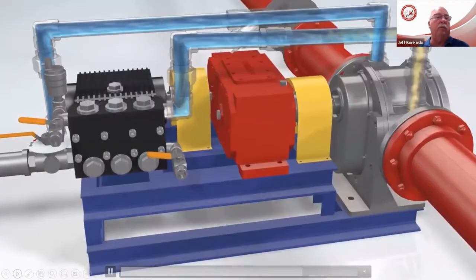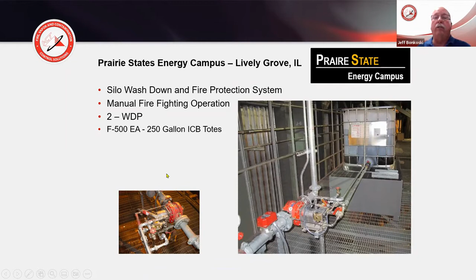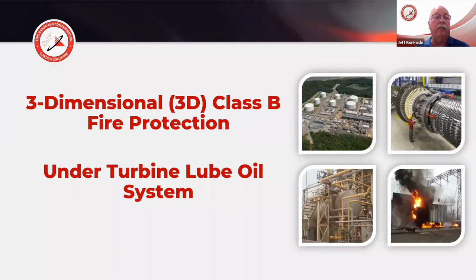Here's an example. We have a tote with a containment, and as you can see, it's elevated, so it's gravity fed. Again, there's no electricity and no pump needed. You have your water driven proportioner and your flow controls. Once the water starts flowing, the pump will activate and draw concentrate up into the water system and the sprinklers, helping to cool. It adds the agent in and works to reduce the soot, toxins, heat and smoke. It works on three-dimensional fires, under turbine lube oil systems, class Bs, all the different types of fires.